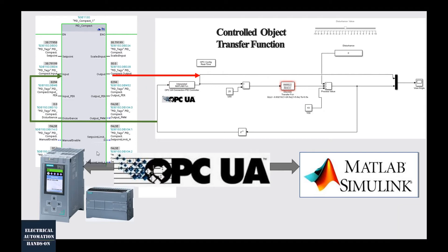Since OPC UA requires a server and client setup, MATLAB will run as an OPC UA client and the PLC will run as an OPC UA server. So in this video, we will mainly discuss how to enable and set up the OPC UA server function in Siemens S7-1200 PLC.